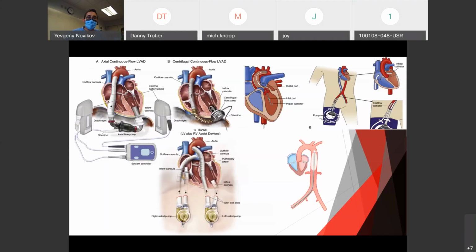So this is showing you an LVAD, different types of LVAD, but quickly it's showing you, again, you have the inflow cannula, which is sitting apically, and it's getting pumped whether immediately or through a secondary thing. And just as a cool thing, these are similar to submarine-based propellers. They're levitating off of a place. They're not attached to anything. They're just turning with a magnetic field and actually producing a flow.